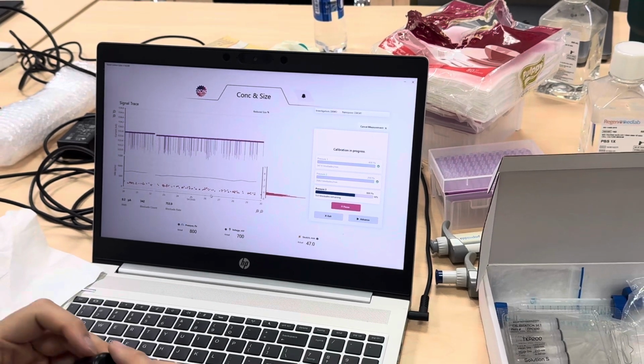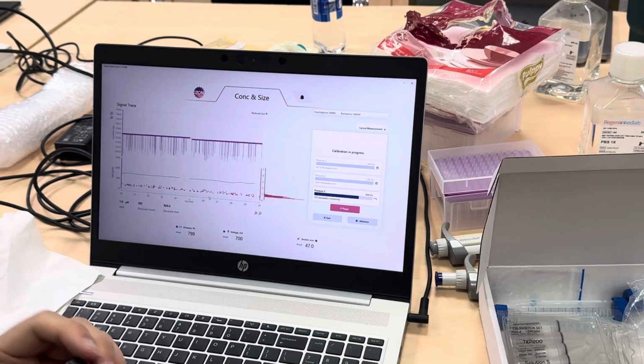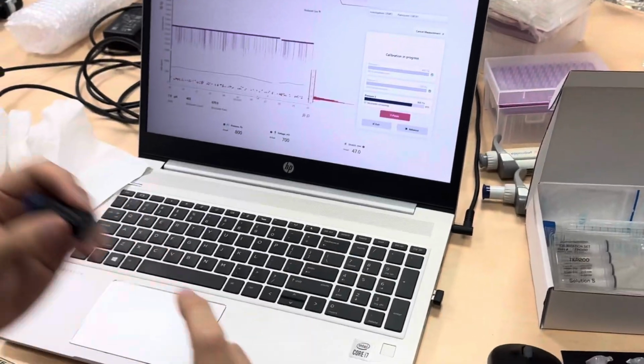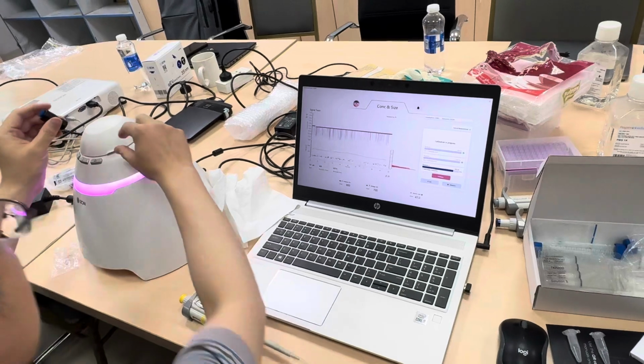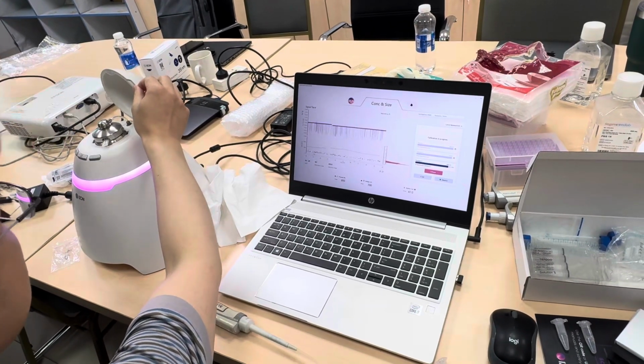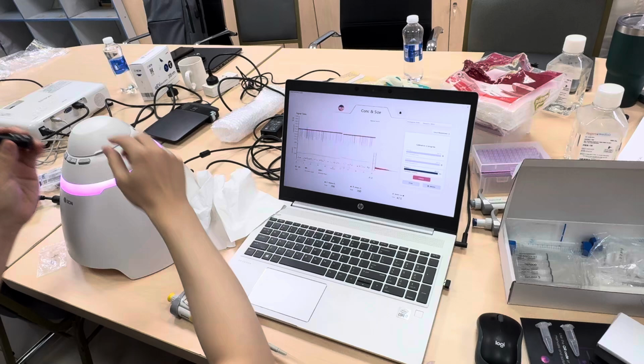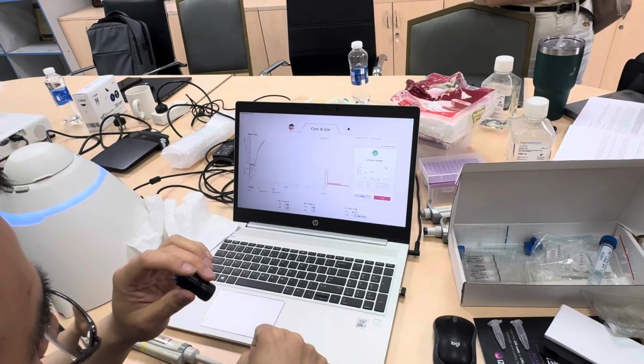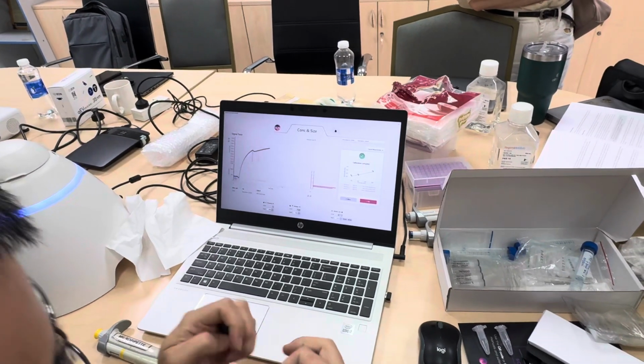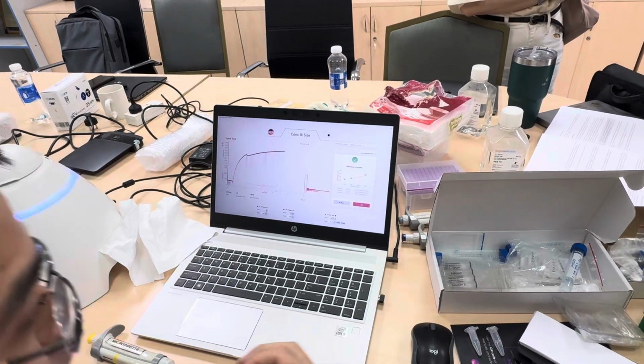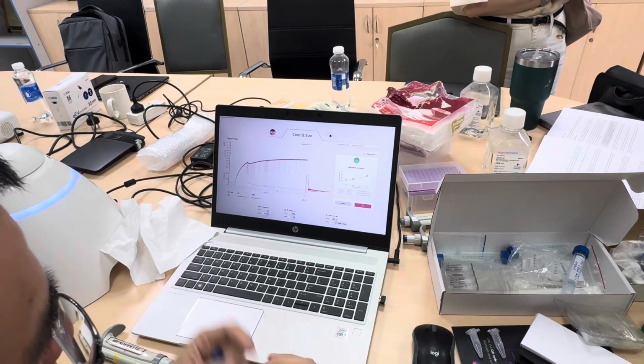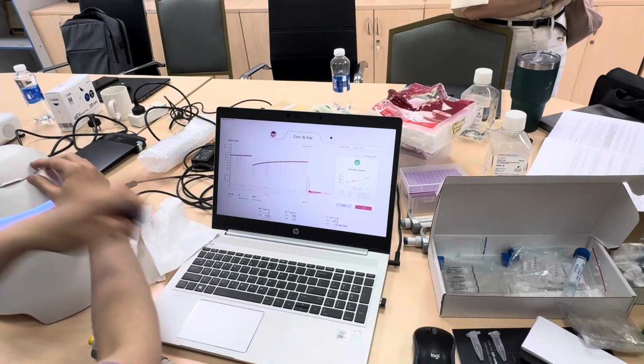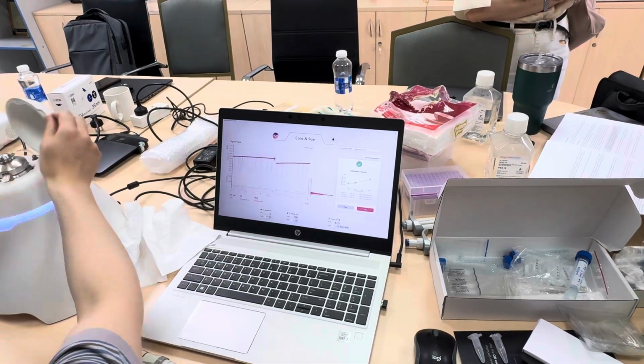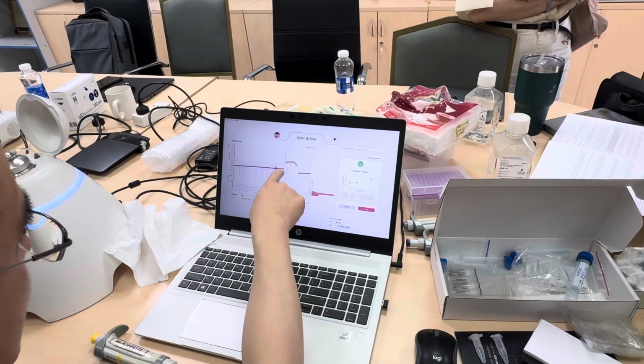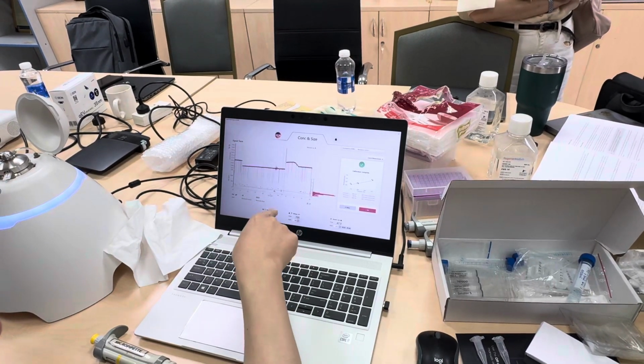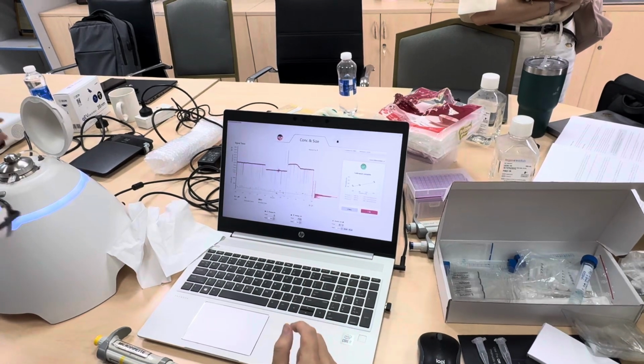So for that, you may use this PAD, called a pressure application device. There are 2 sides. This side is to manually give the system pressure: you tap on the nozzle, because it's metal, so it will not harm the system. Give it instant pressure, and then let the very large particle pass through the nanopore. But you may doubt, does this affect the reading? No, the system has calculated, because the calibration is already done. If you're tapping it, you see there's a trend up and down. So the system will delay that data for your troubleshooting.